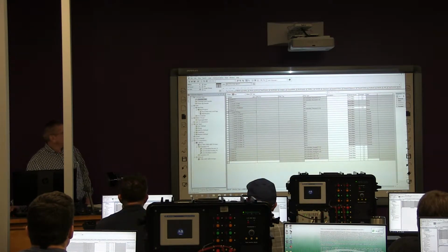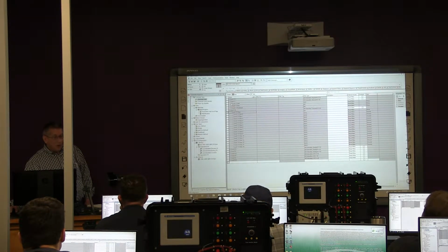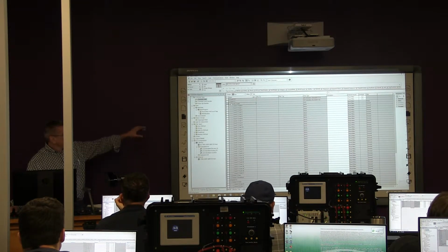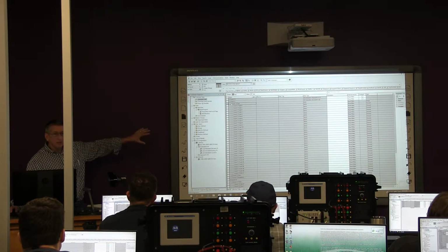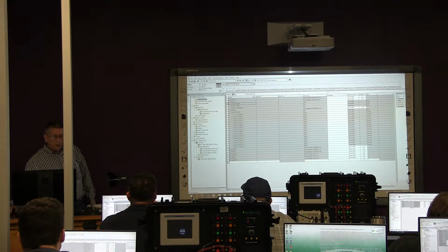And here's the key. The local 1I fault, that's data also. That's the data that we're going to get back from the module itself, right? If you notice, there's 32 bits in this. It's a double integer data type. But when we click on local 1O, there's not a fault data file in there, right?